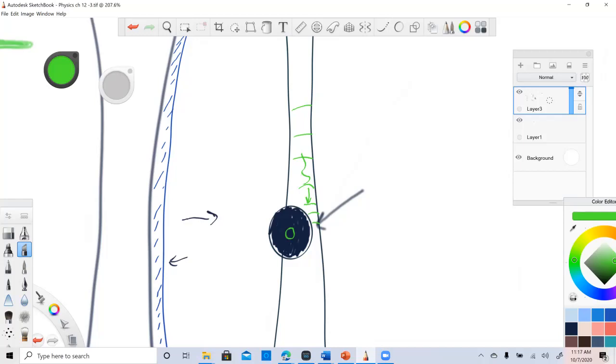And so you end up with fuzz inside of the cyst. There are some other things that can cause that fuzz, but in this case, they're real echoes. They're just slightly misplaced because we weren't thinking about the fact that there's a thickness to this beam.